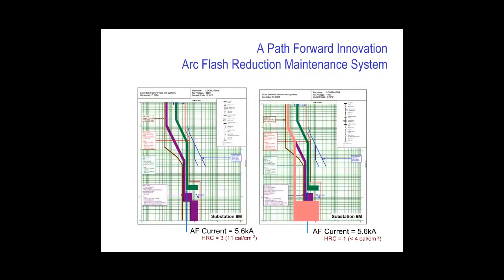Let's walk through an example to demonstrate how the ARMS multiple settings group capability works. What I've shown here is coordination curves for a unit substation. On the left is the setting that you would have for a selectively coordinated system. The main breaker is shown by the green curve and the feeder breakers are shown by the purple curve. You can see both have a short time delay setting. And as you can see on the left-hand curve, if I had an arc fault current, or an arcing current, of 5600 amps, I would be in the short time delay setting of the feeder circuit breaker.